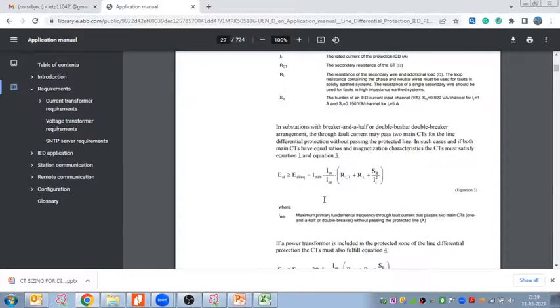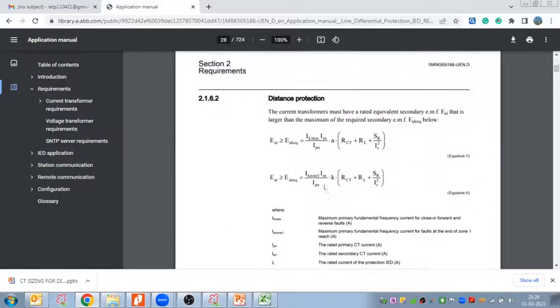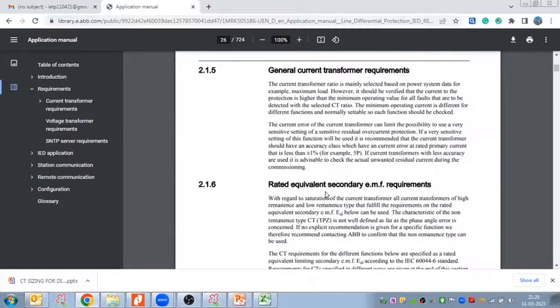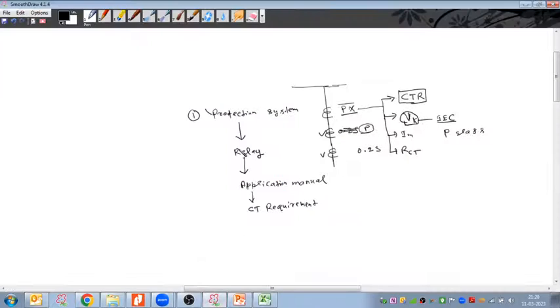If we are using distance protection for short, medium and long transmission lines, in that case we have to select these two equations for the CT knee point voltage calculations. Anyway, we will take both differential and distance, and we will discuss that, right? So how can we decide the protection system and relay? For that we can take the reference of the tender. We can open the tender and read the control and protection philosophy required by the particular client. From that we can understand the protection system requirement.